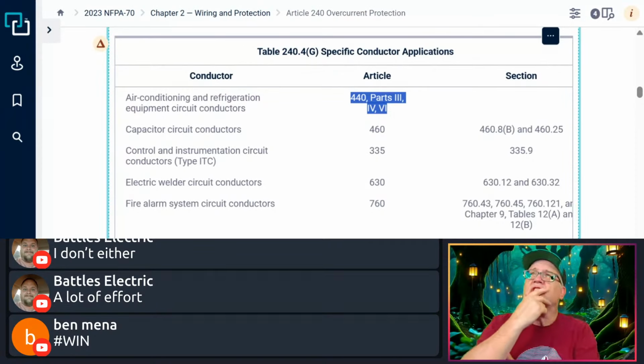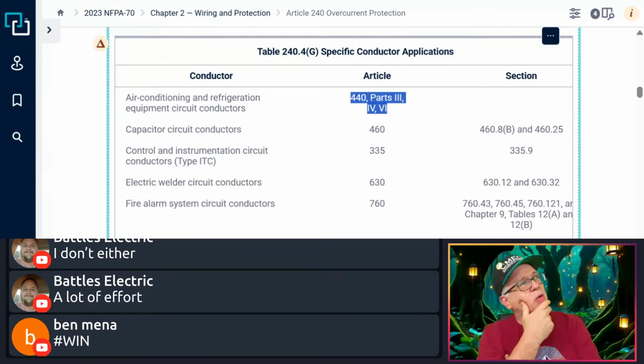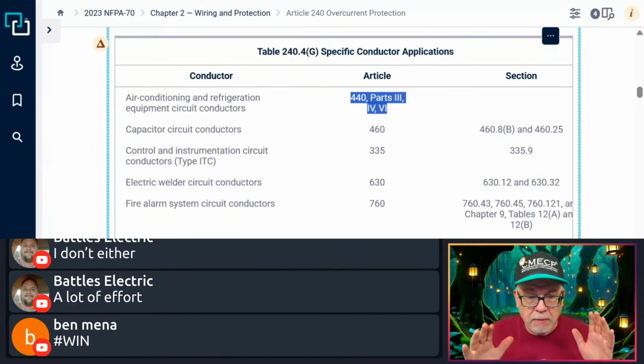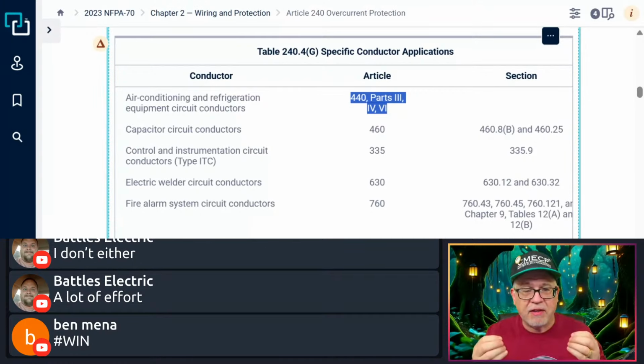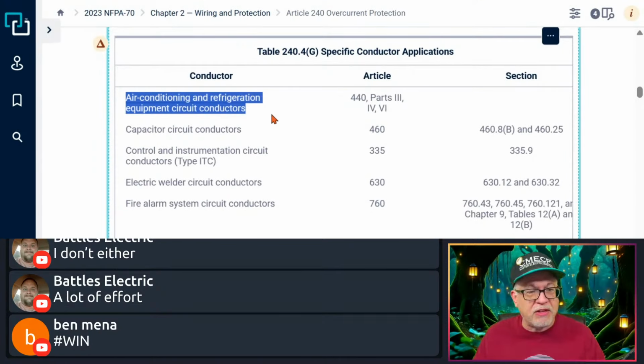Don't say, well, isn't that a continuous load? Don't I have to size that at 125 percent? Stop! You're overthinking it. When it comes to the nameplate on an HVAC unit, just follow the nameplate. I need 23 amps, right? Okay, minimum. All right, so here, it gives me the permission to ignore that 20 amps for a 12 gauge, right? And so under that provision, I'm able to use it at its 75 degree rating, which has 25 amps. So I can put a 12 gauge in it.